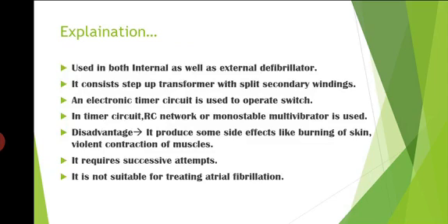It is used for both internal as well as external defibrillation. It consists of a step-up transformer with split secondary windings. An electronic timer circuit is used to operate a switch. In the timer circuit, an RC network or monostable multivibrator is used.